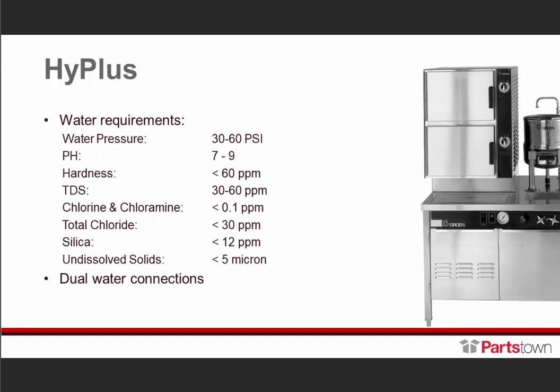The HyPlus is our boiler-based system. It has a 15 PSI boiler inside the cabinet, operating at about 12 PSI. Just like the Hyper Steam, it has instant recovery. It requires traditional deliming, though the deliming requires a technician — the end user does not perform deliming on this unit. It covers every area of application. As you see here, to the right of the cavities there's a kettle, so this unit can also power adjacent equipment, whether a cabinet-mounted kettle or a smaller floor kettle. These are the water requirements for every steamer that requires water treatment, and this unit also has dual water connections.